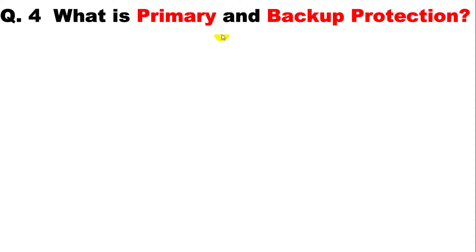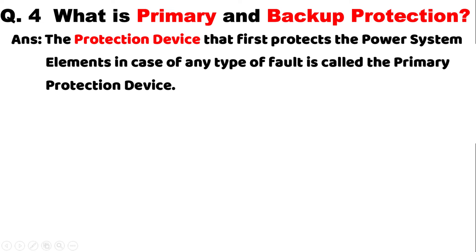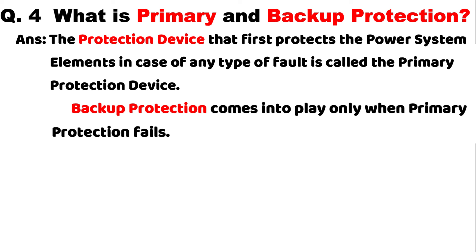The fourth question asks: what is primary protection and backup protection? When any fault occurs, the protection device that first protects the power system elements is known as primary protection. If the primary protection device is not working for some reason, then we use backup protection. Backup protection comes into play only when primary protection fails — if primary protection is unable to break the circuit, backup protection will break the circuit.